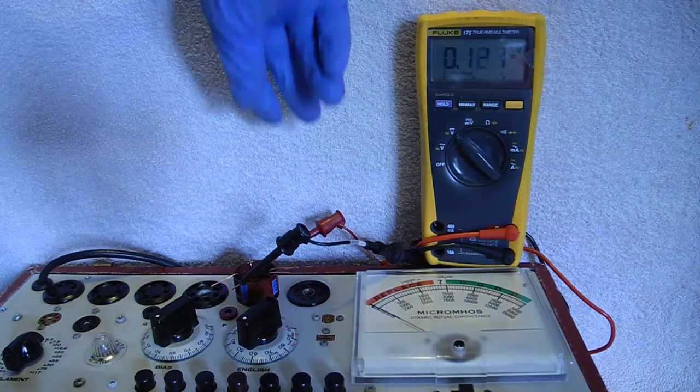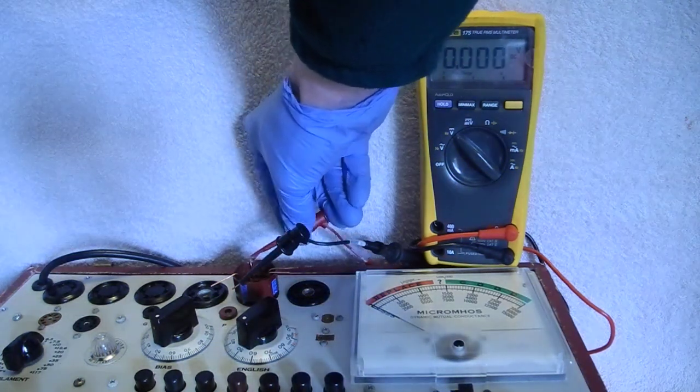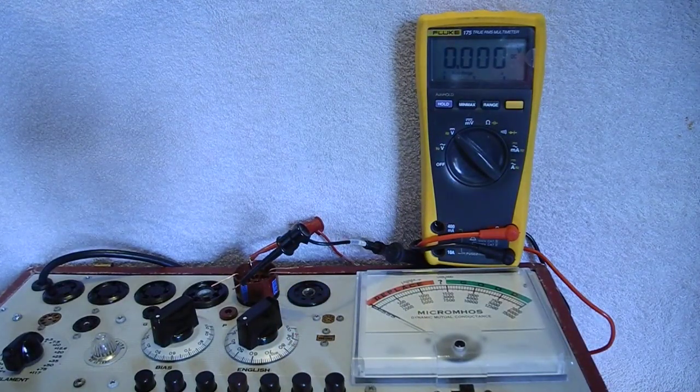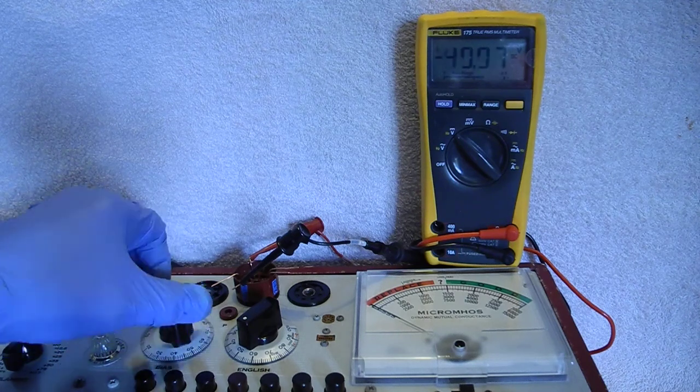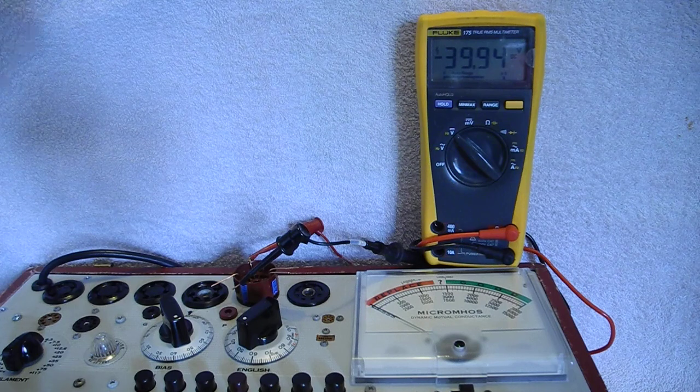The next step is we move our clip over to the grid, which is pin 5, and we check our grid bias voltage at a bias of 100. It should be negative 40 plus or minus 2 volts.